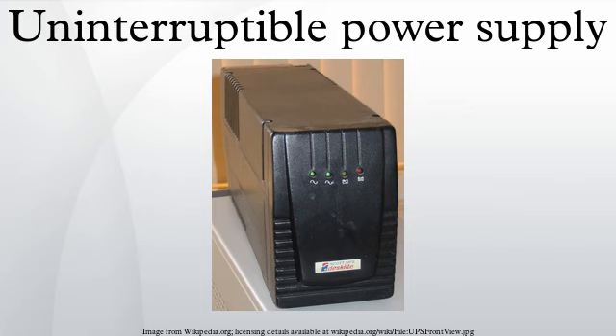Online double conversion. In an online UPS, the batteries are always connected to the inverter, so that no power transfer switches are necessary. When power loss occurs, the rectifier simply drops out of the circuit and the batteries keep the power steady and unchanged. When power is restored, the rectifier resumes carrying most of the load and begins charging the batteries, though the charging current may be limited to prevent the high-power rectifier from overheating the batteries and boiling off the electrolyte. The main advantage of an online UPS is its ability to provide an electrical firewall between the incoming utility power and sensitive electronic equipment.